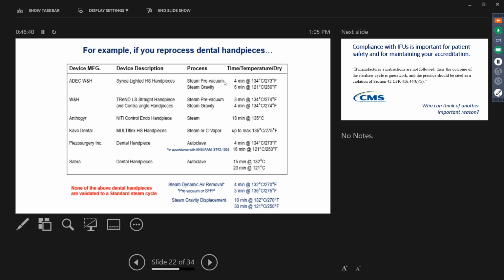And it's 4 minutes or 16 minutes. Not a single one of them are validated to a standard cycle, which is what I'm validating the tabletop sterilizer to - our standard cycles and their test lab. Not a single one. Not one of them.